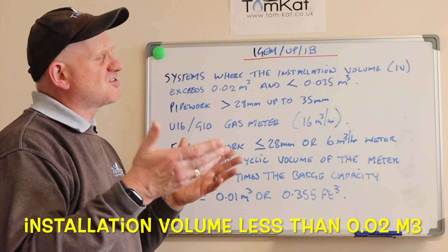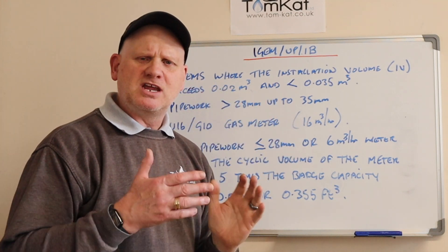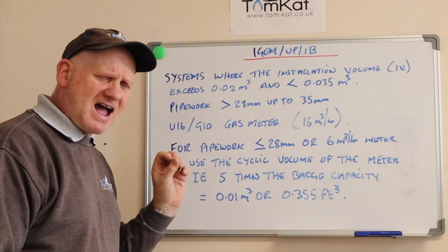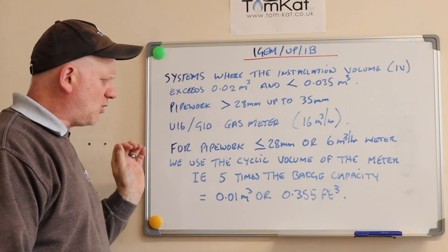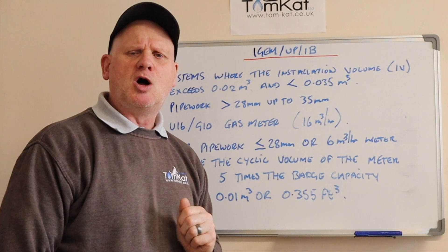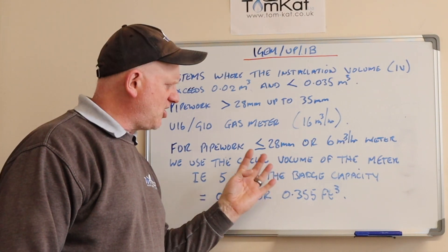The other way of purging applies to a small domestic property, where pipework is equal to or less than 28 millimetres and the gas meter is only giving us six metres cubed per hour — so an E6, U6, or G4 gas meter. The way we do that is we use the cyclic volume of the meter: five times the badge capacity, which equals 0.01 metres cubed or 0.355 cubic feet if using old cubic feet meters.